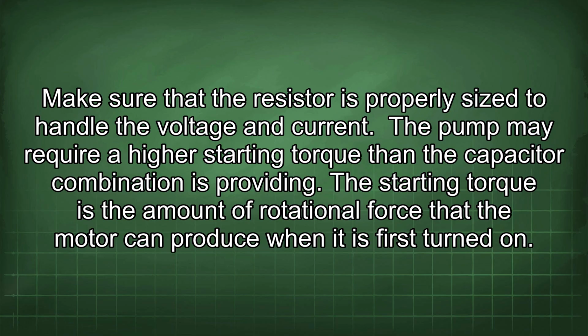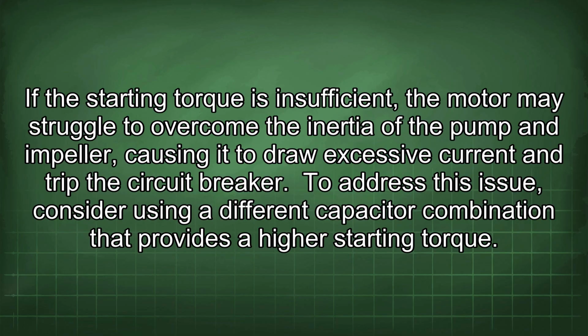The pump may require a higher starting torque than the capacitor combination is providing. The starting torque is the amount of rotational force that the motor can produce when it is first turned on. If the starting torque is insufficient, the motor may struggle to overcome the inertia of the pump and impeller, causing it to draw excessive current and trip the circuit breaker.